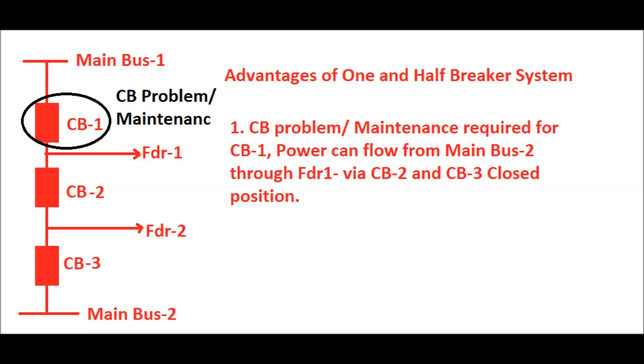What are the advantages of the one and half breaker system? First, consider a circuit breaker problem in CB1 — the main bus 1 side circuit breaker — or if CB1 requires maintenance. In this case, feeder 1 still gets power from main bus 2 via CB3 and CB2 in closed positions, and feeder 2 also gets power through main bus 2 via CB3. So if CB1 is under maintenance or has a fault, feeder 1 and feeder 2 still receive power from main bus 2 with no interruption.